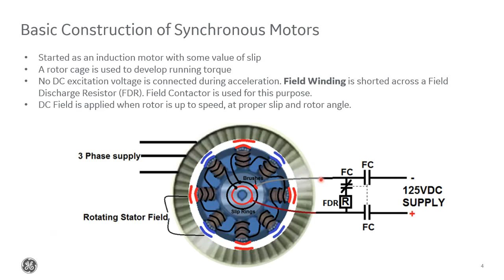So to start as an induction motor, the DC excitation system is disconnected via this field application system. The field contactors keep the circuit open, while there's usually another normally closed contactor here with a field discharge resistor connected in series. The purpose of this field discharge resistor is to give a path whenever the DC field is inactive so that the current induced in the field windings by the stator is limited. Otherwise, it could potentially damage the windings.